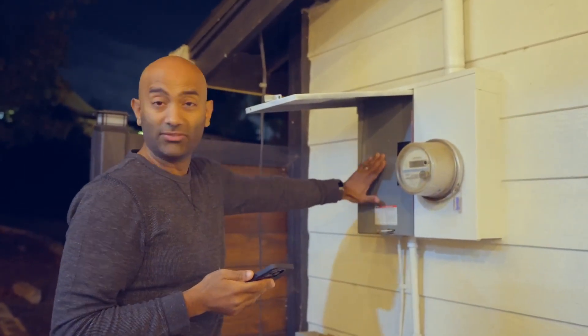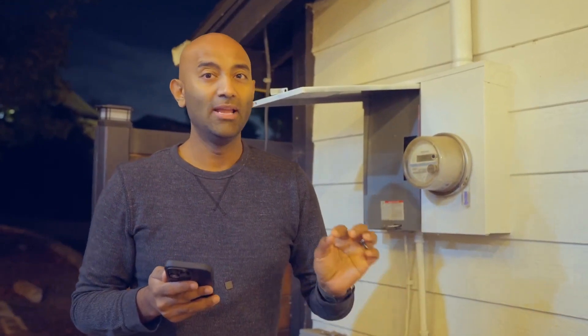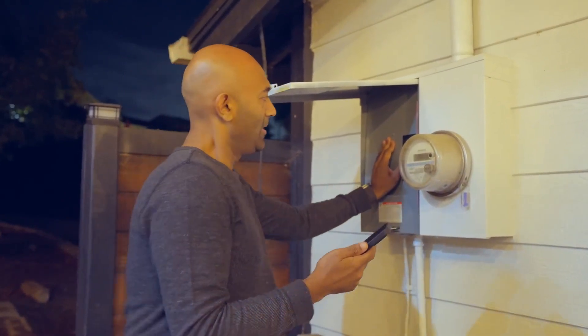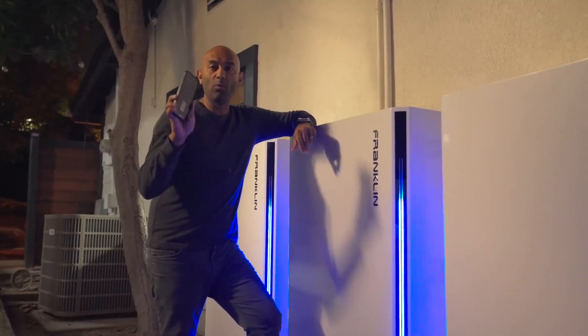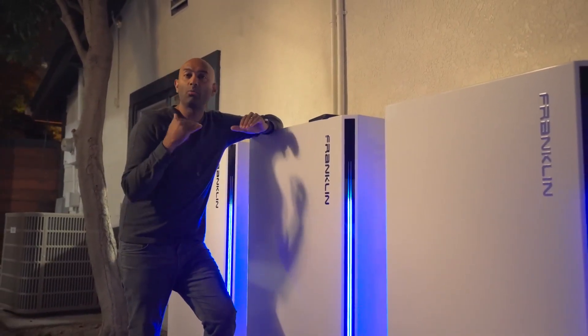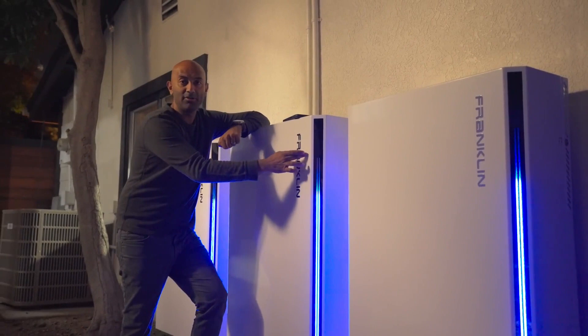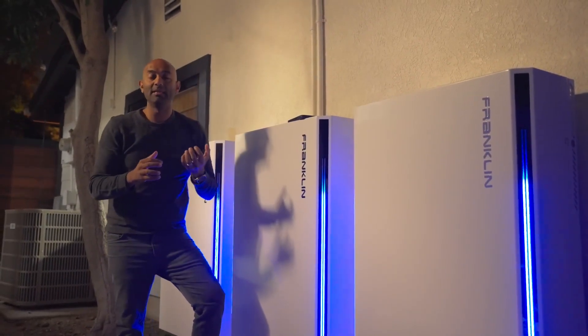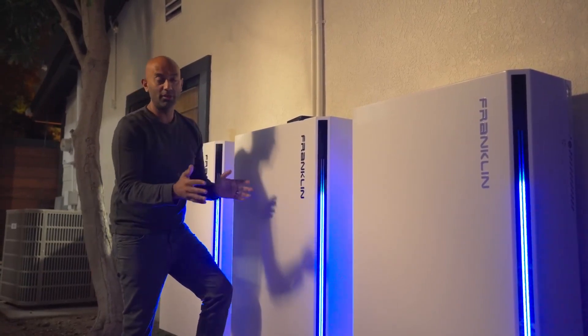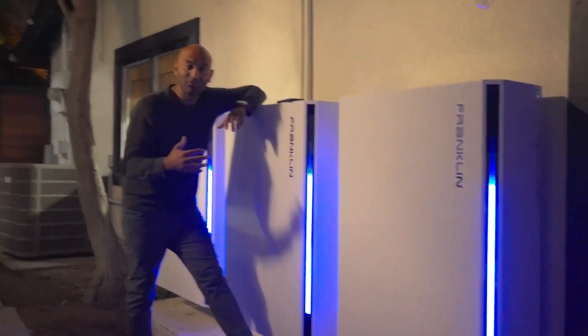As I mentioned before, the grid is off currently, but when I turn it back on it won't just immediately switch back over. It'll wait and monitor and make sure everything's good. Let's see how that looks right now — grid back on. While we wait for the grid to come back online, let me share a couple other things I noticed about the battery. If the power were to go out and the batteries were entirely full, the solar panels would be turned off. It waits for the battery to discharge to about 90% before taking incoming solar input. So when the batteries are full, to prevent any overloading or overcharging, it doesn't take any more solar input until after it drops down to about 90%.